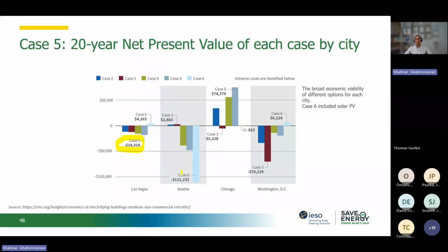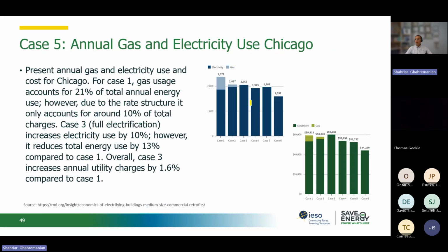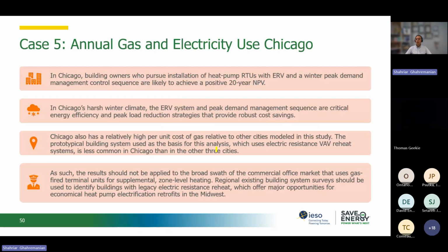If you look at the life cycle, a 20-year operation of the facility, including the initial cost, which is the purchase and installation of the system, you see that there are many savings available to the commercial building, and it has a positive net present value for these cases. There are also natural gas savings, because we are switching from a fossil fuel burning system to electricity, electrifying the building. That's going to be another benefit of switching to these heat pumps. Again, they did not account for that in their NPV calculation, but if there are taxes on natural gas, that can also be considered and added to the calculation, similar to Canada.